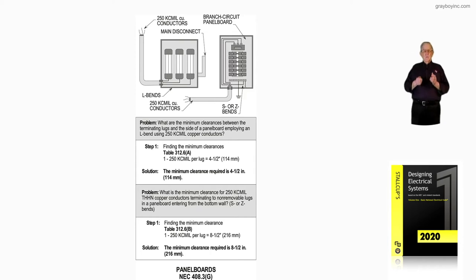Notice when you review the illustration to the left, that's an L bend. You bring it in and you bend it in an L. That is an easier bend to terminate because you can pull it towards you, you can stab it easy, and your clearance rules are not as great.